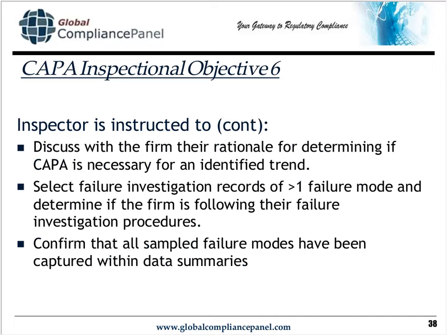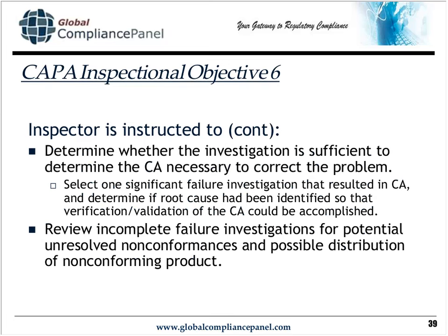And for every failure mode that they look at when they sample these multiple failure modes, they're going to look at your data summaries and your trends to make sure that these sampled failure modes have been captured in there. They're going to look at whether your investigation was sufficient to determine the necessary corrective action.